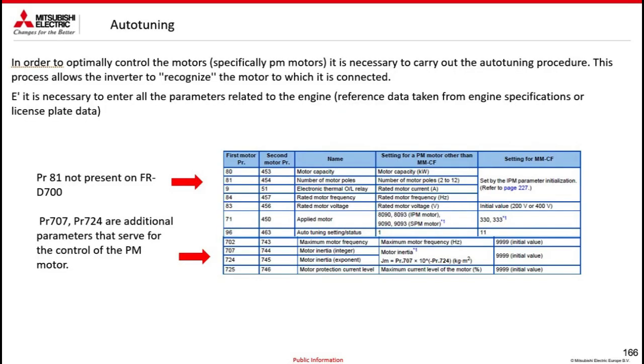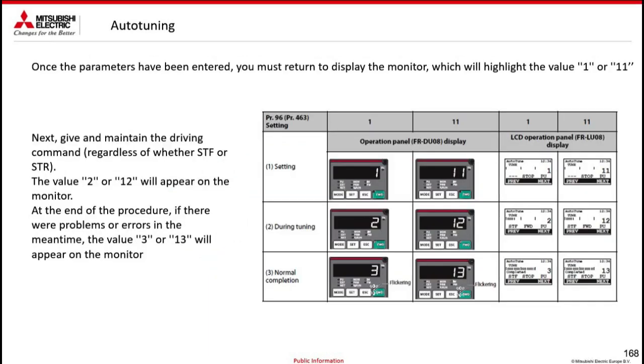Then I fill in the number of poles, the nominal power, the nominal voltage, the frequency, the voltage induced on the windings, the inertia of the motor, and the negative exponent of the inertia of the motor. Once I have done this, I will perform the auto tuning, which is as I explained before, but here in this slide it is repeated. Once I have performed the tuning, it is ready to work.